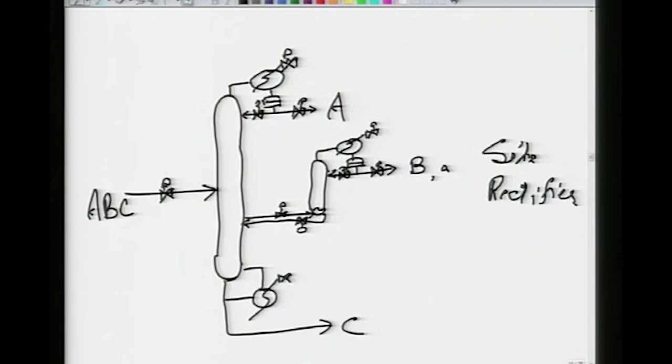Alright. So, let us see. These are all the independent valves. Feed is not in my hands, it is coming from an upstream process, for example, the reactor. So, total number of valves excluding the feed is 1, 2, 3, 4, 5, 6, 7, 8, 9, 10. So, I have got 10 valves that can be adjusted. Of these 10 valves, one would go for main column pressure control. One valve which probably would be this guy, you see these guys, the ones in blue will go for pressure control.